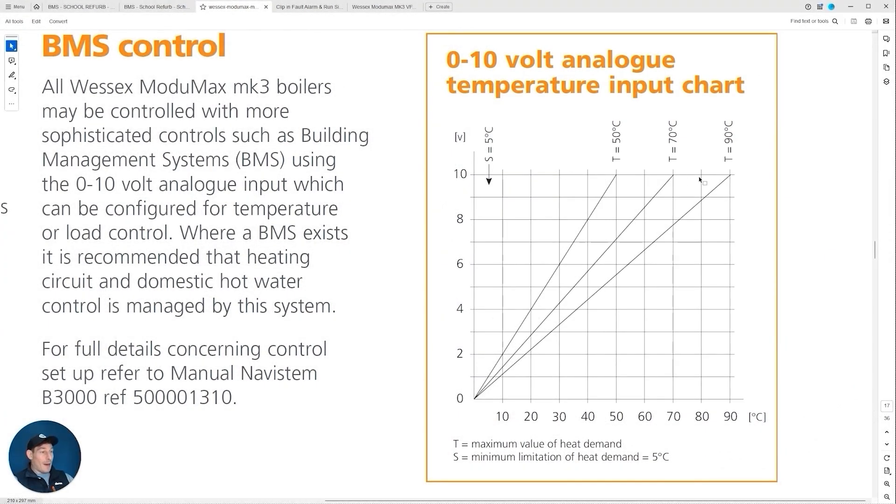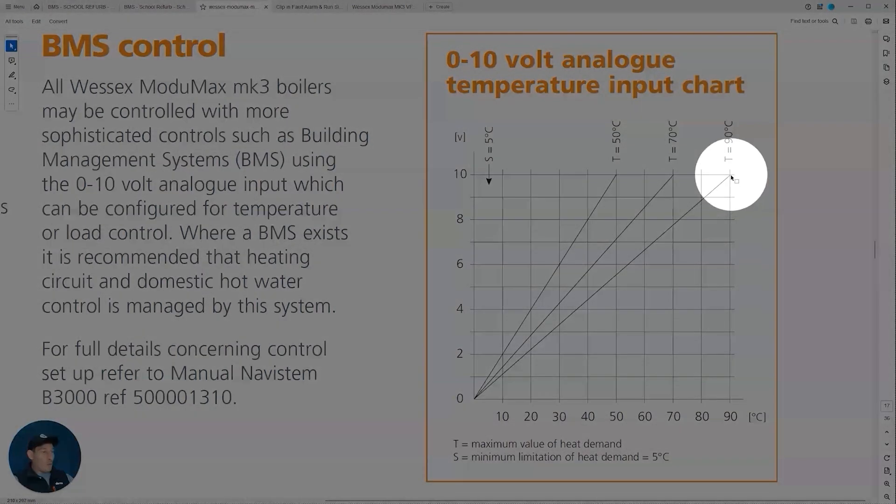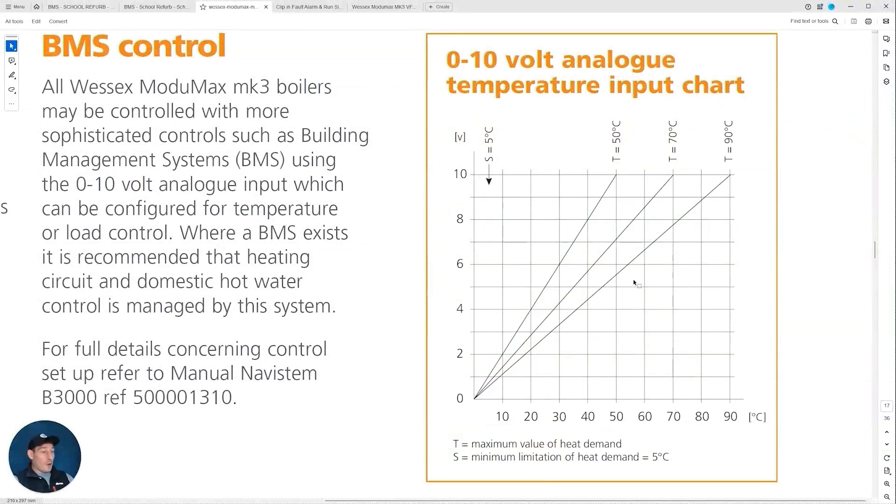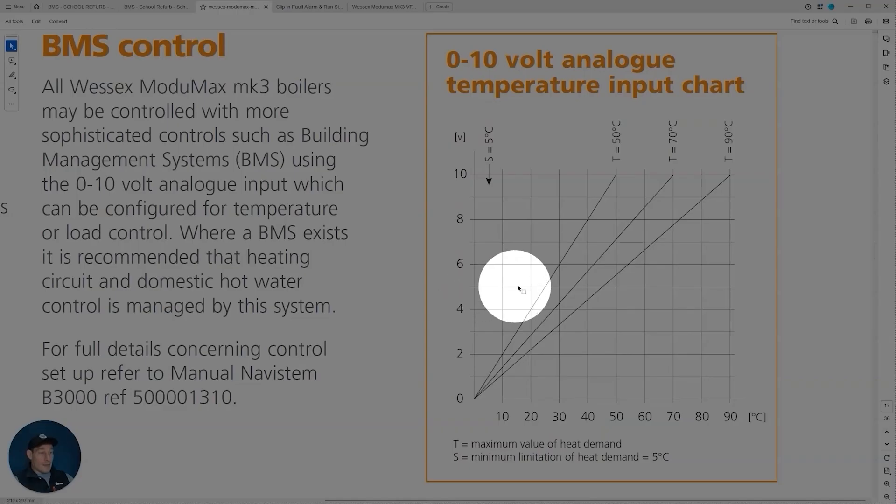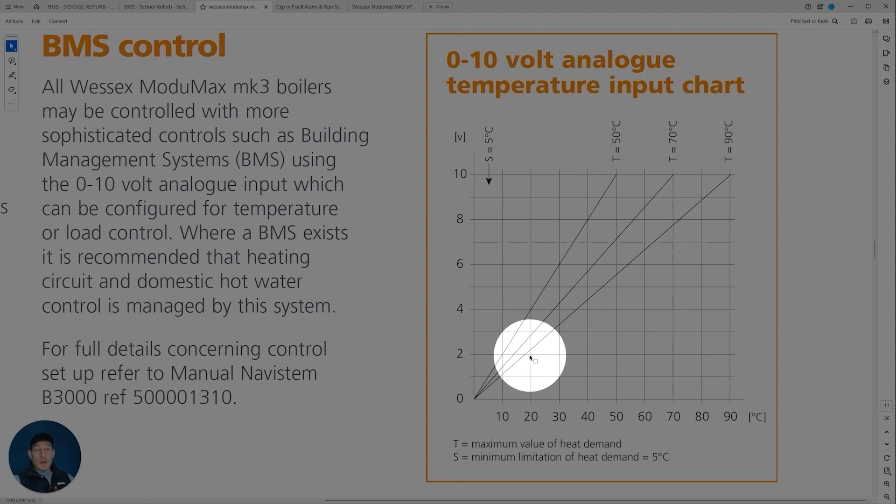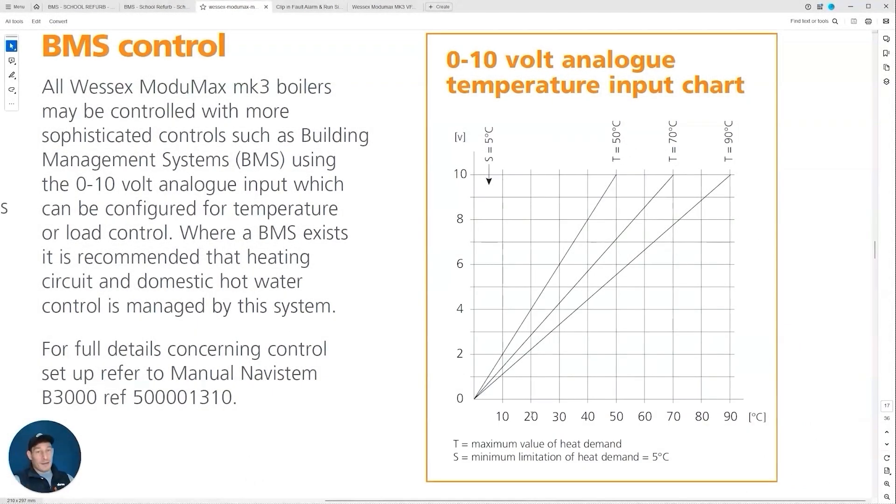Now if we go five volts, that's mapping to 45 degrees. So this is just the graph that tells us when we feed the boiler say two volts it's gonna correlate to about 20 degrees C and so on and so forth.